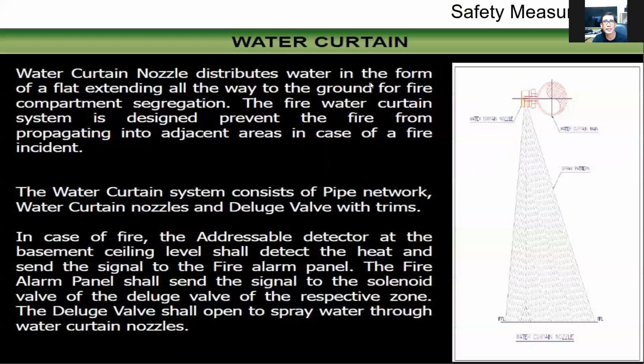So now we also have what you call the water curtain nozzle. It distributes water in the form of a flat sheet extending all the way to the ground for fire compartment segregation. This fire water curtain system is designed to prevent the fire from propagating into adjacent areas in case of a fire incident. It is usually used in buildings like coliseums, churches, or convention areas, where you can put a water curtain to prevent the fire from going from one open big space to another open big space. So this is what you call a water curtain.